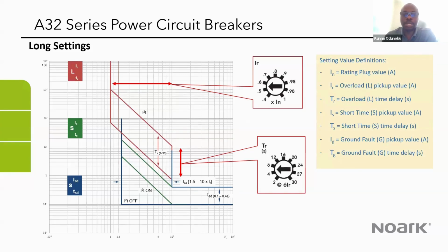So just to run quickly through the types of settings that you have in the electronic trip unit, you can have the long time protection, which is what we call the overload protection, and it has an inverse time function, meaning that as the current is increasing, you have a shorter response time for the overload protection. If the current increases very quickly, then the reaction time reduces. You can introduce a delay as well for that, and you can have particular settings for the overload. It could be from 0.4 all the way to 1 of the rated value that you protect for.